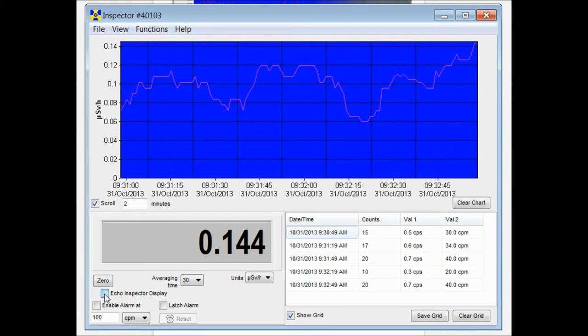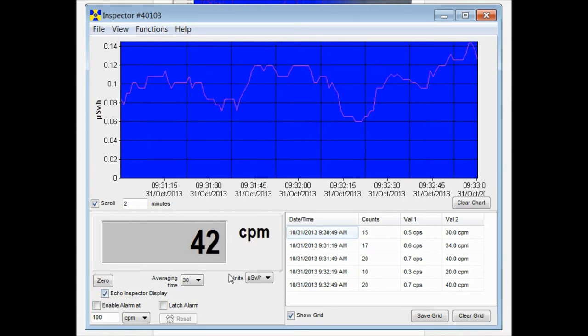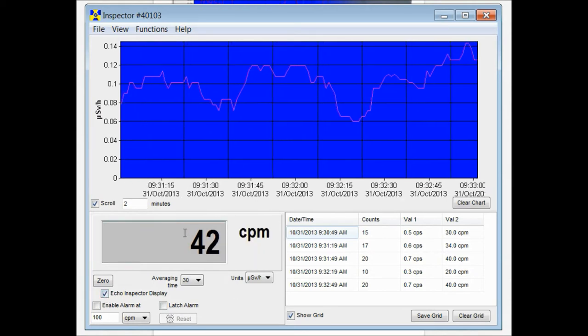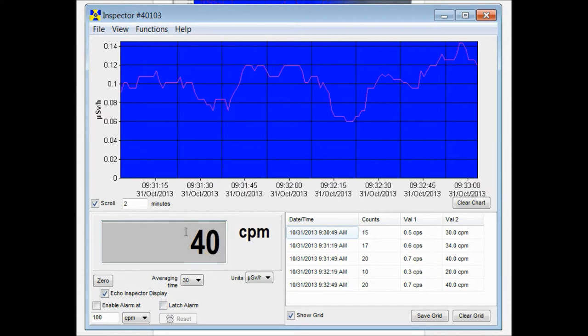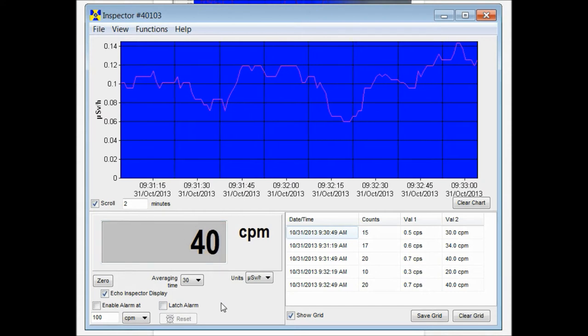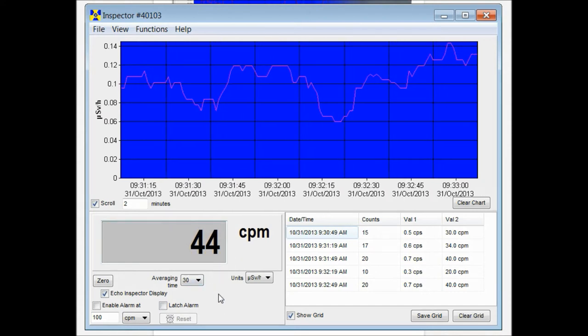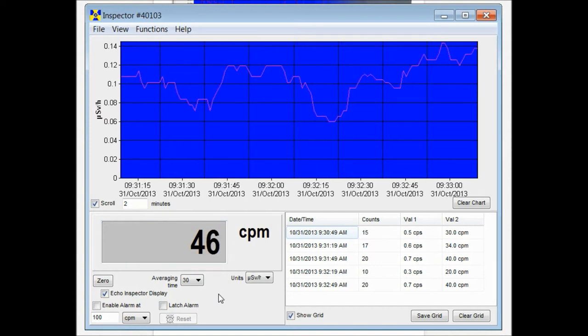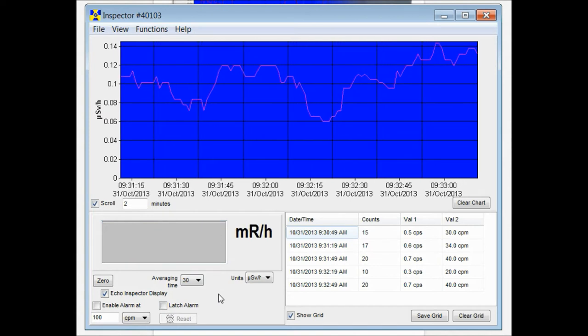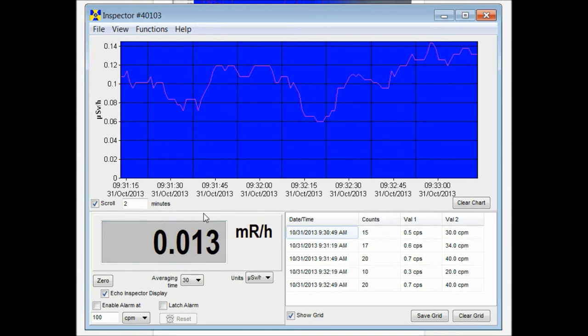Now you click this echo inspector display and that's going to echo the display of your unit. Say right now I have the unit in CPM. If I change the unit of measurement on the mode switch to mR per hour, that's reflected in the observer software window as well.